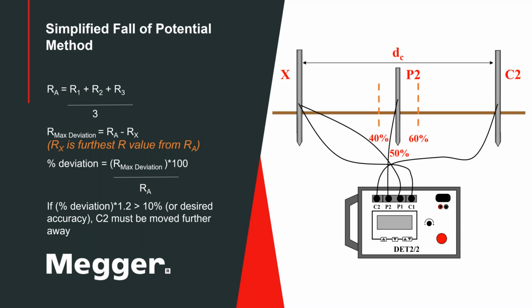And now the obvious question here is, well, suppose I just looked at the measurements and made a decision. Well, yes, that's what a lot of veteran operators do. They don't really bother with the math. They just do what you could call the eyeball method. They move the probe back and forth, and they look for the conformance between those 3 measurements. Well, if they're all exactly the same, you're really good.